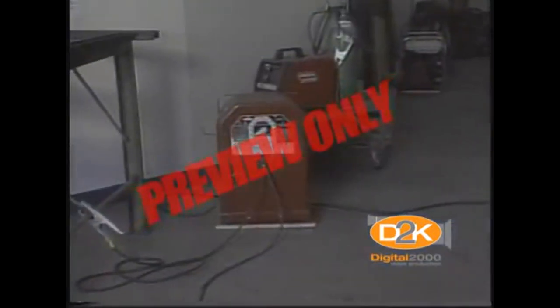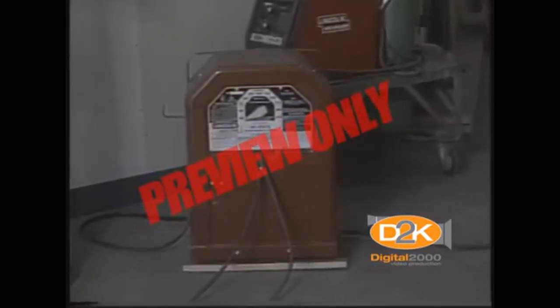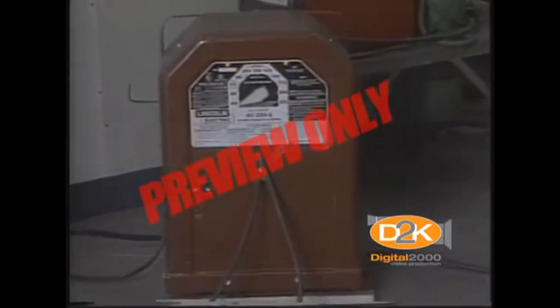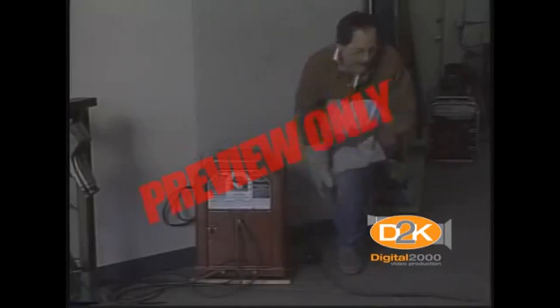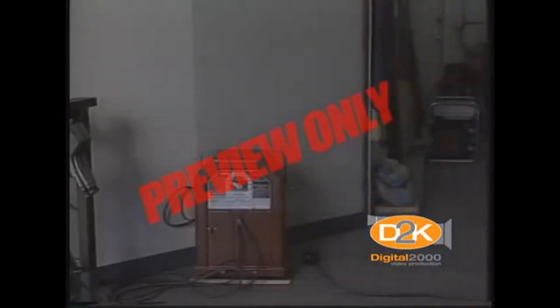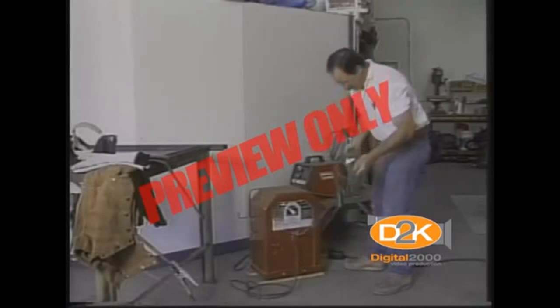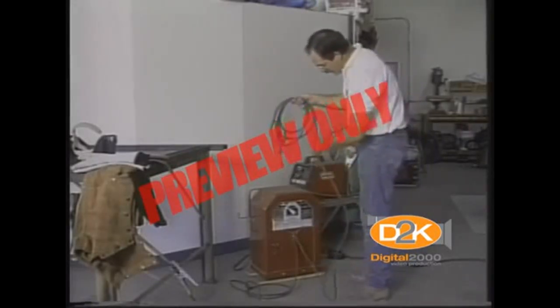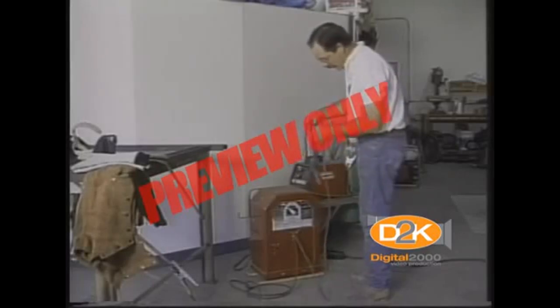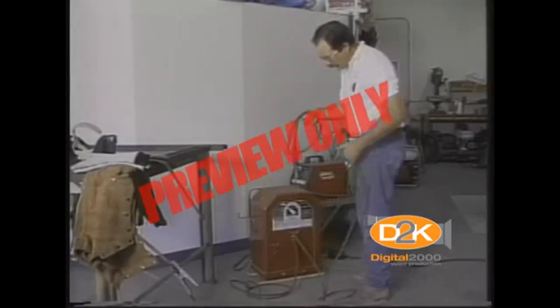Don't operate arc welders in wet environments and dry all machines and equipment that have become wet before attempting to weld. Before drying wet equipment, make sure you disconnect the primary power first. When making connections and cabling, spread out coiled welding cable prior to use and check weld lead cables for damaged insulation and work lead cables for exposed conductors. Replace all weld leads spliced within 10 feet of the holder.